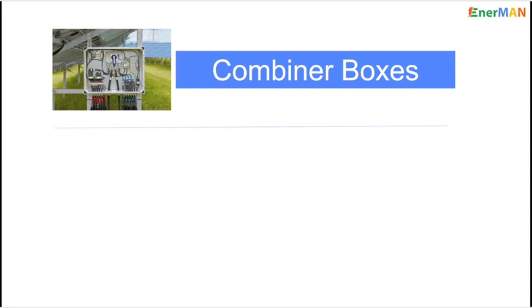So I'll start with the combiner boxes — one of the critical equipment, especially when you need to monitor the string. In most cases we see, the monitoring sensor PCB or the entire sensor board has failed or burnt.